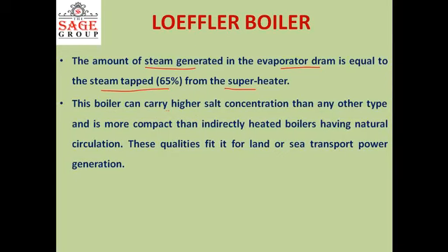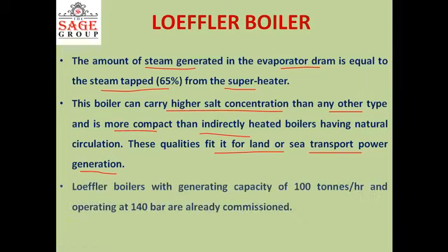Now this boiler can carry higher salt concentration than any other type of boiler and is more compact than indirectly heated boilers having natural circulation. These qualities fit it for land or sea transport power generation, because in the coastal areas there is a lot of salt in the water, and in that case it is very difficult to operate any boiler other than the Loeffler type, because salt deposition is a major problem.